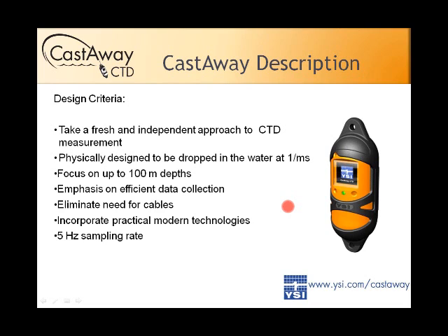The Castaway has a terminal velocity that keeps it falling at about one meter per second without any added weight. Another constraint was focusing on shallow water — less than 100 meters deep. Estimates suggest 50 to 75% of all CTD casts are made in those depths, and there's not really a specific device for that. The emphasis was on usability and efficient data collection — eliminating the need for cables or connectors, incorporating modern technologies such as GPS and Bluetooth, and sampling at 5 Hz to ensure proper data.